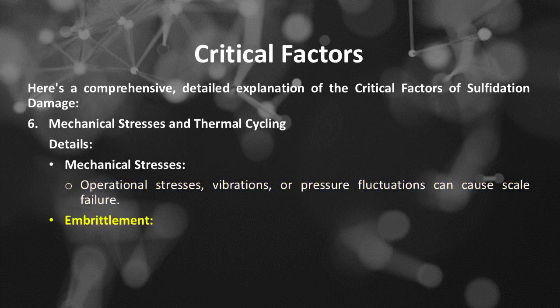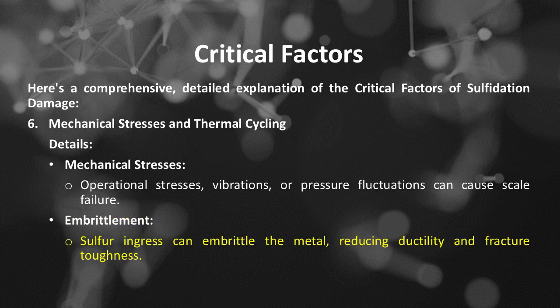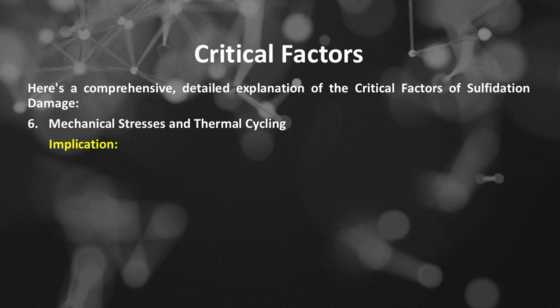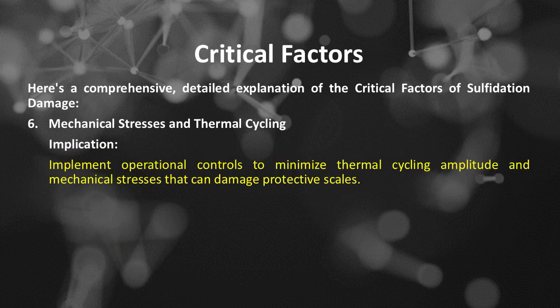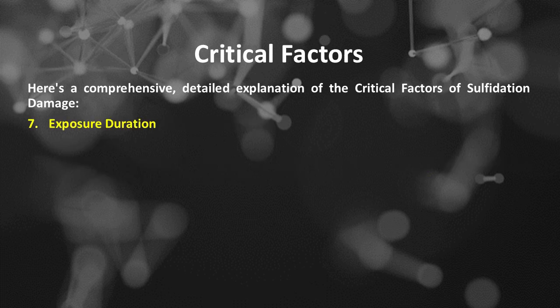Mechanical stresses and thermal cycling embrittlement. Sulfur ingress can embrittle the metal, reducing ductility and fracture toughness. Mechanical stresses and thermal cycling implication. Implement operational controls to minimize thermal cycling amplitude and mechanical stresses that can damage protective scales. Number 7 of critical factors of sulfidation damage is exposure duration.